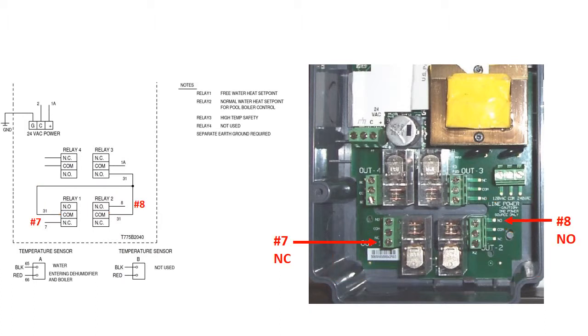The normally open terminal on relay 2 connects to the number 8 terminal on the dehumidifier. And on relay number 1, it is the normally closed terminal that connects to number 7. Relay number 4 is not used on this example.